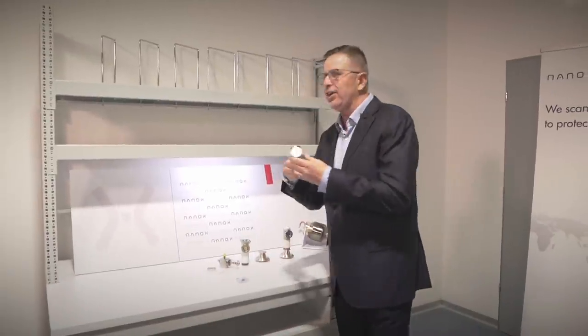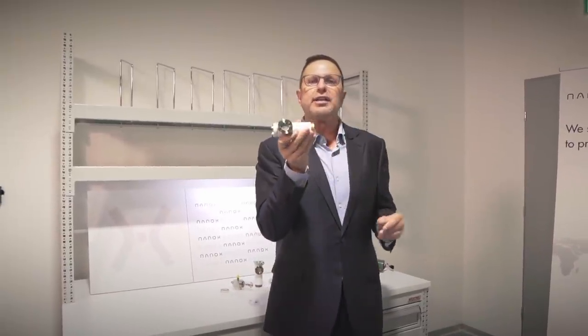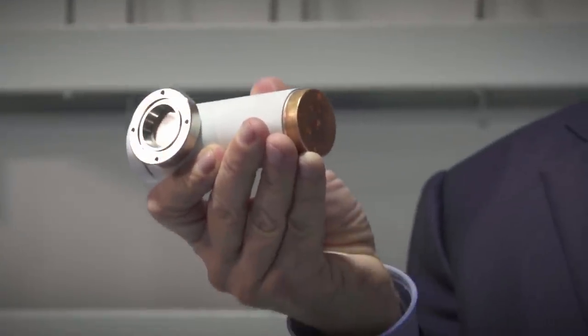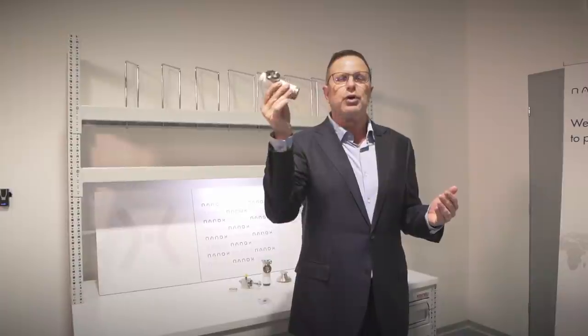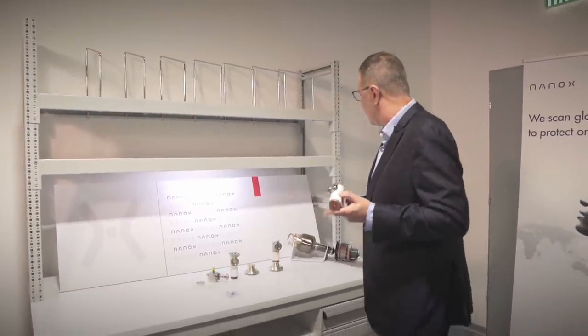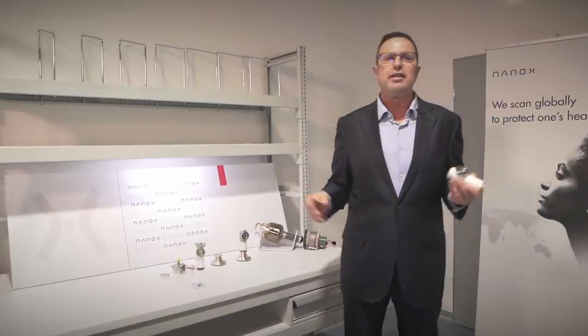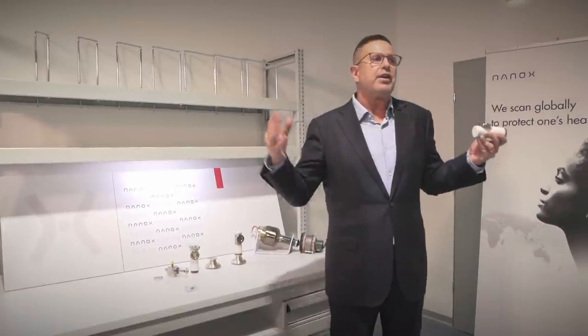And this is Nanox X-ray tube. This is the core technology that we have. This is the first ever nanotechnology tube that can go the entire range of X-ray, that can play with mA and kV independently, and it's very low cost, so much low cost that you can place many of those, hence our vision to propel the universe with those light bulbs that can actually give very good images, as you'll see in a minute. Now, just for comparison, you need to understand that what we have here is a traditional, typical X-ray thermionic source. We have the glass, we have a rotating anode, we need to rotate it via an engine, and we put all of this in a basin of oil, and that entails a lot of limitations. So that's basically the technology that we've developed.